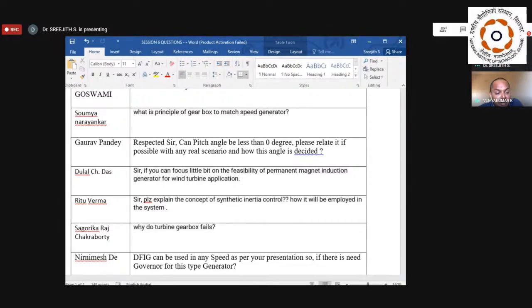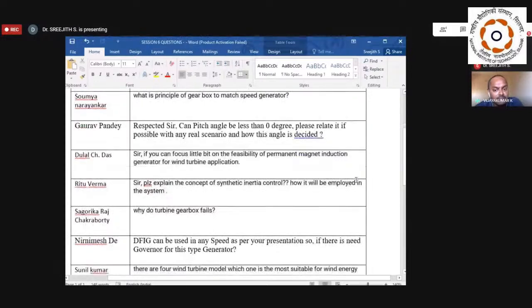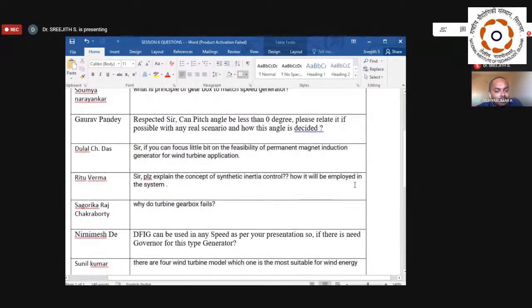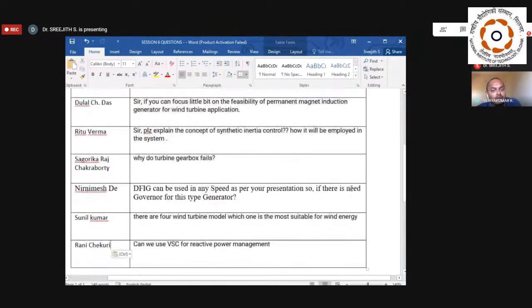Here I want to clarify that there is no permanent magnet induction generator. It's a permanent magnet synchronous generator. Permanent magnet synchronous generators can be used for low power applications as well as in the megawatt range. Even gearless wind turbines prefer permanent magnet machines.